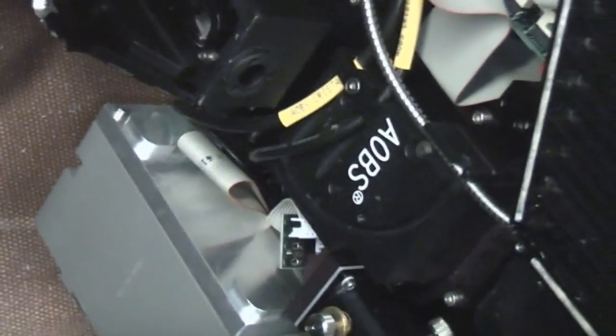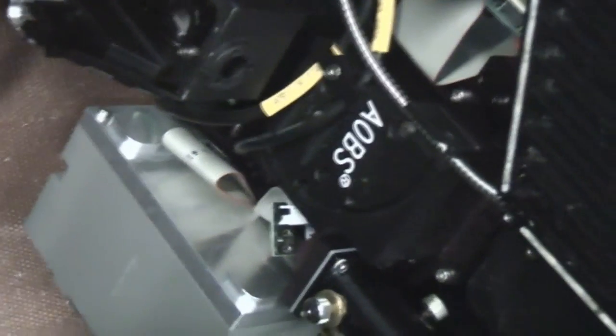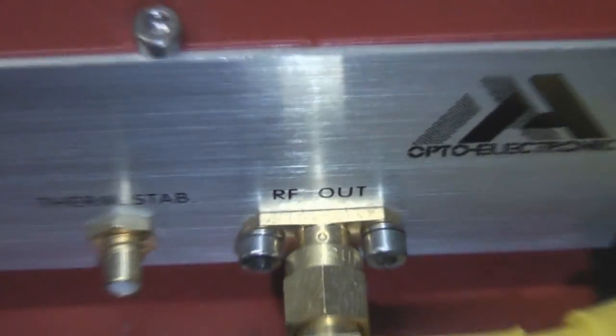Now, one thing I did find when I was hunting around for info, and it's also mentioned here, is this AOBS. That stands for Acousto-Optic Beam Splitter. This is a very clever electro-optical device that basically appears to select a wavelength based on an electrical signal. So it's like an electrically tunable prism, which is rather an interesting piece of tech. Also here it says a caution, AOBS must be connected before turning on. Now these things, like a lot of electro-optical devices, use RF excitation, so you can see on these boxes here it says RF out. And of these boxes, two of them, the RF seems to go out to the head unit. This one actually connects down to here.